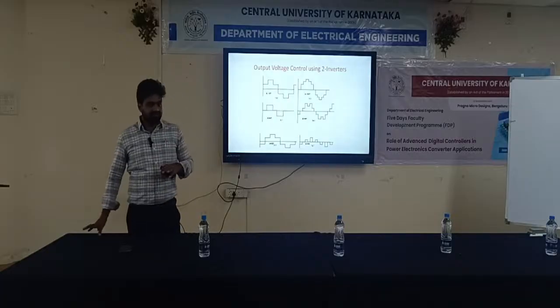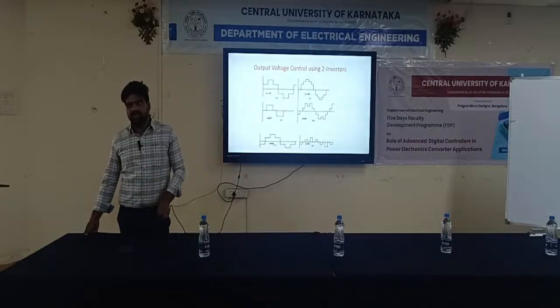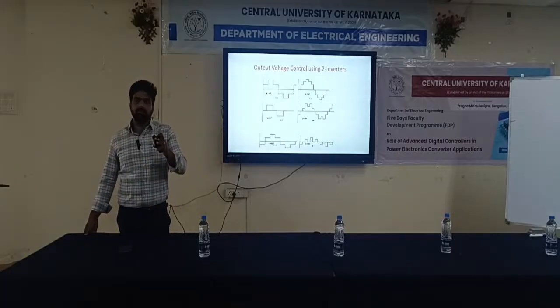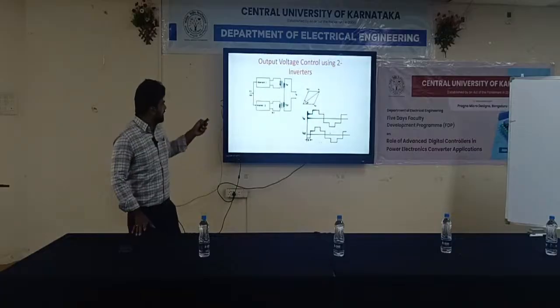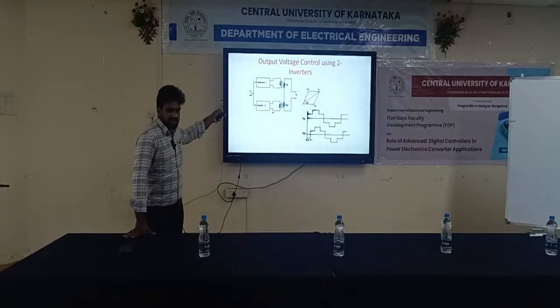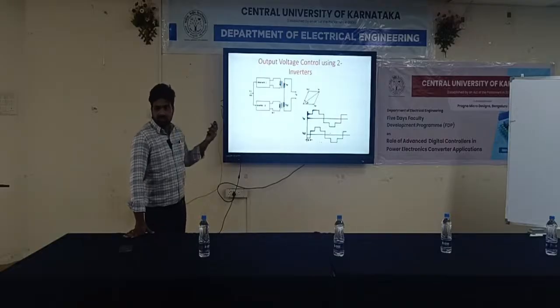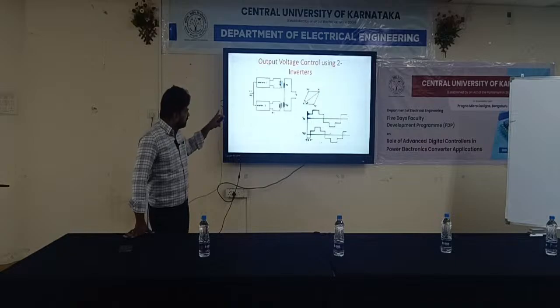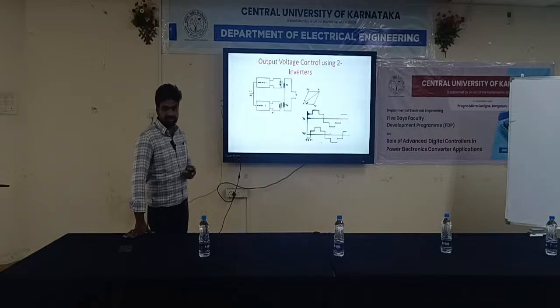That phase shift is generally calculated by 360 degrees divided by the pulse number. Here the inverter is a 6 pulse inverter, so with two such inverters you get a total of 12, and 360 divided by 12 gives the phase shift of the transformers.